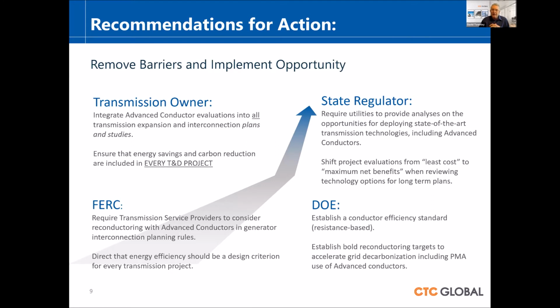For the state regulator, they should be looking at advanced conductors being deployed all through the system, anywhere the interconnection is being made. Reconductoring should be looked at as one of the first go-to choices, to see if that makes a rapid capacity increase, enabling that new generation to come on. And the regulator should shift from a least cost, lowest first cost, to a maximum net benefits approach when they're looking at this.